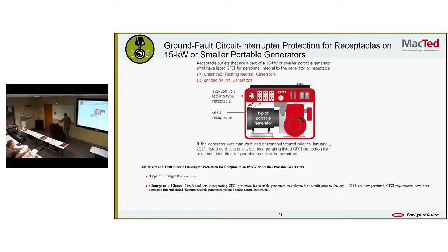Ground fault circuit interrupter protection for receptacles on 15 kW or smaller portable generators. Here's your house generators, RV generators. It says listed cord sets incorporating GFCI protection for portable generators manufactured or rebuilt prior to January 1st, 2015 are now permitted. GFCI requirements have been separated into unbonded floating neutral generators versus bonding neutral generators. So after January 1st, 2015, receptacle outlets that are part of the 15 kW or smaller need to have listed GFCI for personnel integral to the generator or the receptacle. Once again, more and more of that GFI because it saves lives.